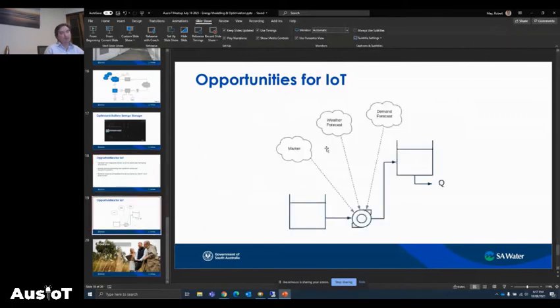From a demand response point of view, if we start to factor in market prices for energy, maybe looking at the weather and what our demand is going to be from customers, we can quickly envisage an incremental step away from that very basic control method into something more sophisticated that predicts what the price for energy might be, what the weather might do, and what customer demand might do. We can make better decisions, saying: well, maybe the tank's a little empty, but the price for the next 3 hours is going to be more expensive, so I might turn on a little later and defer that pumping run by a couple of hours to avoid a price spike in the energy market. You can easily see that would give us a lot of cost reduction just by taking that small step away from level-only based control.